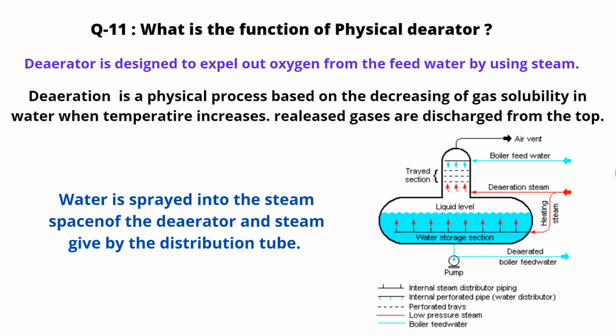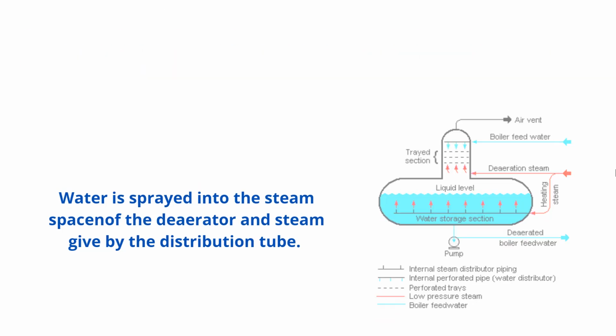What is the function of the physical deaerator? The deaerator is designed to expel oxygen from the feed water by using steam. Deaeration is a physical process based on the decrease of gas solubility in water when temperature increases. Released gases are discharged from the top. Water is sprayed into the steam space of the deaerator and steam is given by the distribution tube.